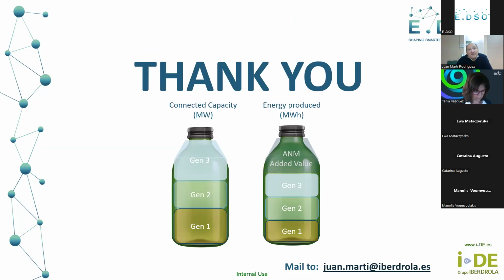At the moment, we are planning to use these logics for parallel transformers, which were not designed to work in parallel, and for typical reactive power control in a distributed energy resource, such as a capacitor that connects or disconnects based on power factor. It's very interesting, and the good news is we don't need any additional maintenance, database, parallel systems, or extra licenses. That's all from me.